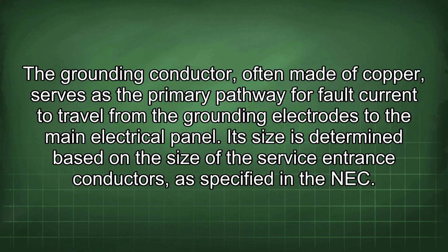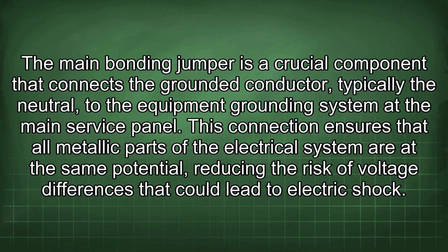The grounding conductor, often made of copper, serves as the primary pathway for fault current to travel from the grounding electrodes to the main electrical panel. Its size is determined based on the size of the service entrance conductors, as specified in the NEC. The main bonding jumper is a crucial component that connects the grounded conductor, typically the neutral, to the equipment grounding system at the main service panel.